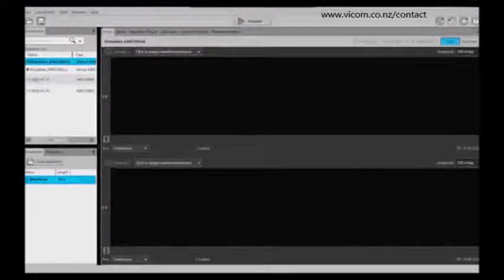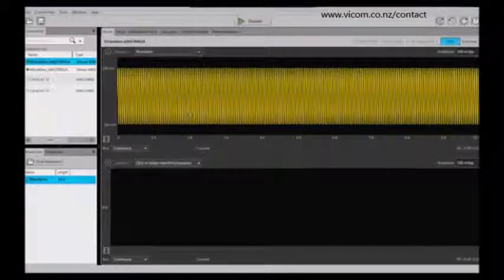You also notice here that I have two IP addresses of instruments that I am connected to through the LAN interface. So these instruments I can actually send waveforms to through the Ethernet. This enables me to create all the waveforms on my PC and my workstation, and then just drag and drop the waveforms into the channels that are connected to that particular connection that I have.